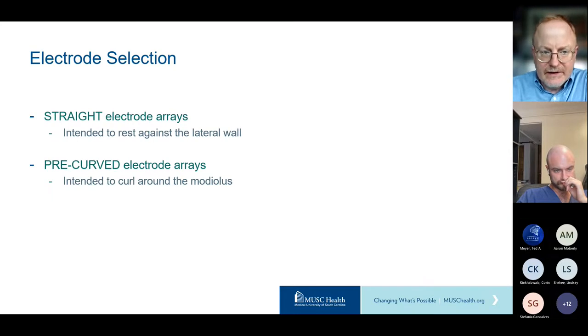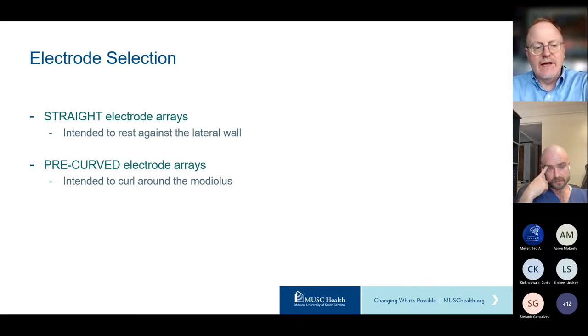The electrode selection component we use is a little bit different than MedEl's, mostly because MedEl only offers straight electrode arrays. Before I talk about this, I really want to harp on the point that I think we should be calling these electrode arrays by their resting state shape—the state the electrode array is in when it comes out of the box without a stylet or without anything holding it. Just if you lay it down on the surgical field, what shape is it?